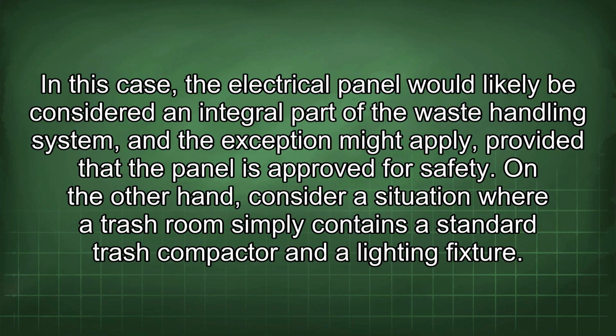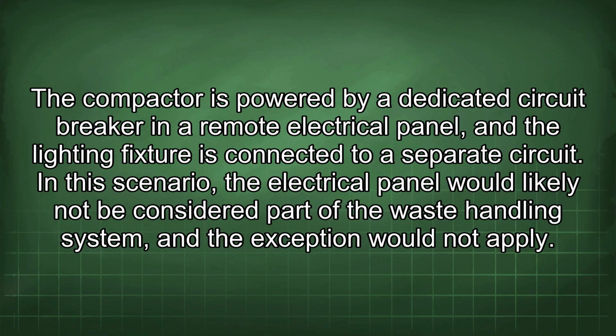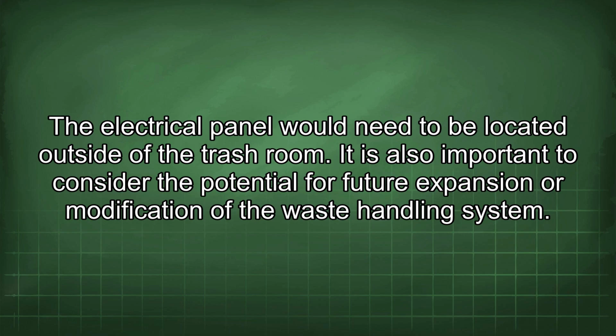On the other hand, consider a trash room that simply contains a standard trash compactor and a lighting fixture, with the compactor powered by a dedicated circuit breaker in a remote electrical panel and the lighting on a separate circuit. In this scenario, the electrical panel would likely not be considered part of the waste handling system, and the exception would not apply. The panel would need to be located outside the trash room.